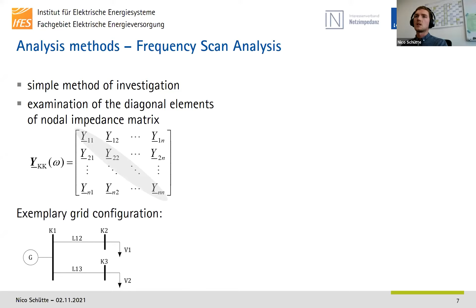Starting with frequency scan analysis, that's the most simple method of investigation, and it is mainly the examination of diagonal elements of the nodal impedance matrix, or it's also possible to do it with the admittance matrix. Using it for such an exemplary grid configuration consisting of 3 nodes, 2 lines, 2 loads, and a generator, it's possible to get different curves and to identify potential resonances. There are probably 3 of them, the first one, the second one, and the third one. But it's observable that these resonances overlap mutually. So the problem with this method is that the characteristic values of these resonances depend on the node they are observed from.